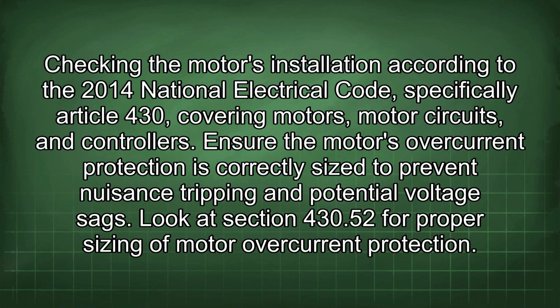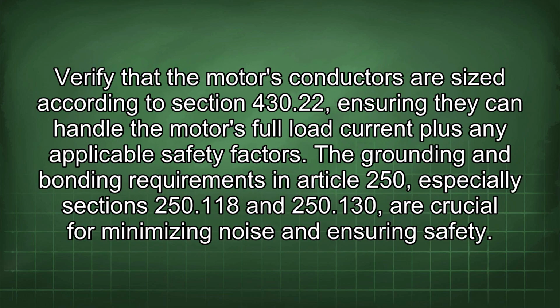Checking the motor's installation according to the 2014 National Electrical Code, specifically Article 430 covering motors, motor circuits, and controllers. Ensure the motor's overcurrent protection is correctly sized to prevent nuisance tripping and potential voltage sags. Look at section 430.52 for proper sizing of motor overcurrent protection. Verify that the motor's conductors are sized according to section 430.22, ensuring they can handle the motor's full load current plus any applicable safety factors.